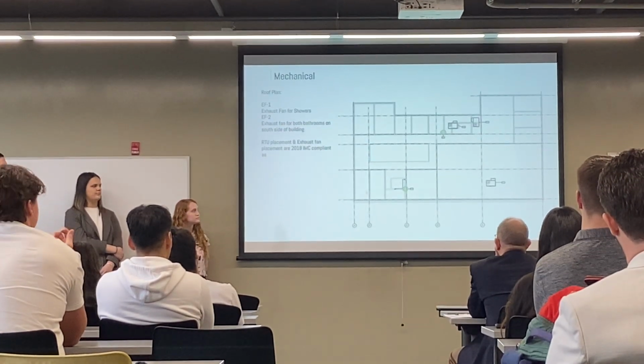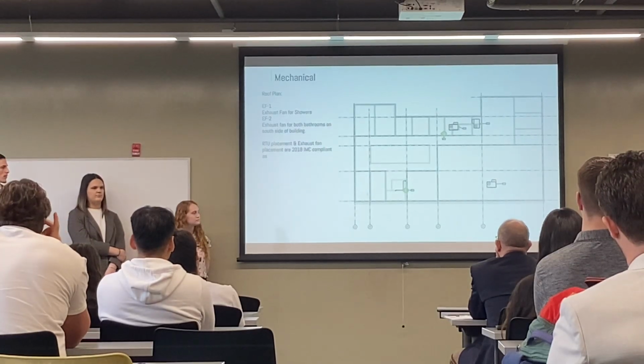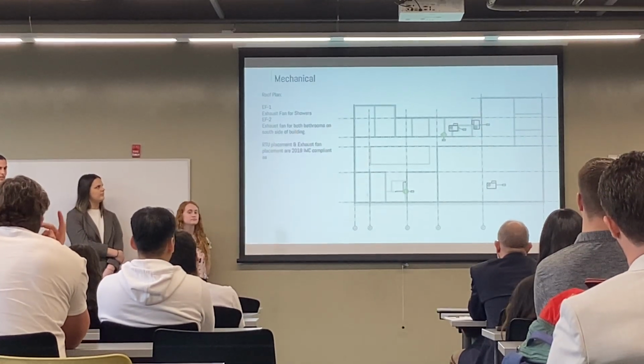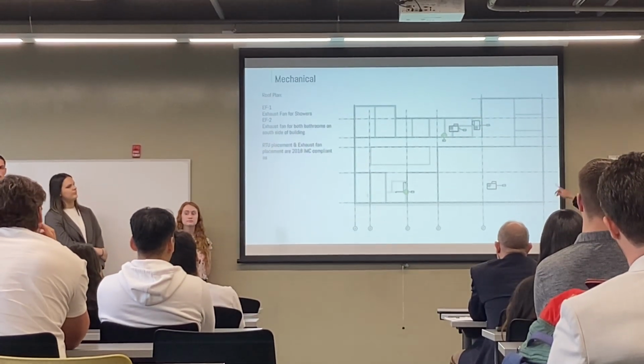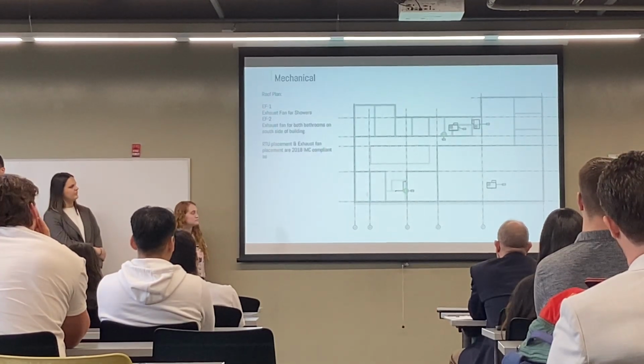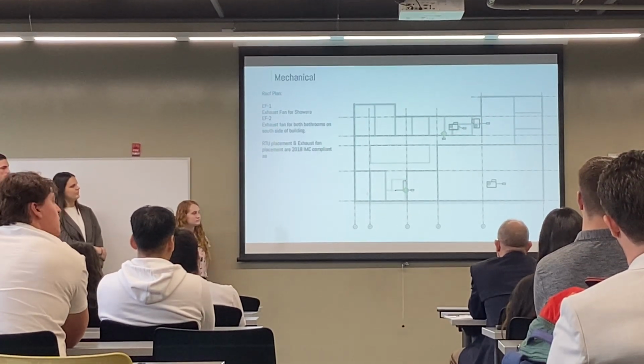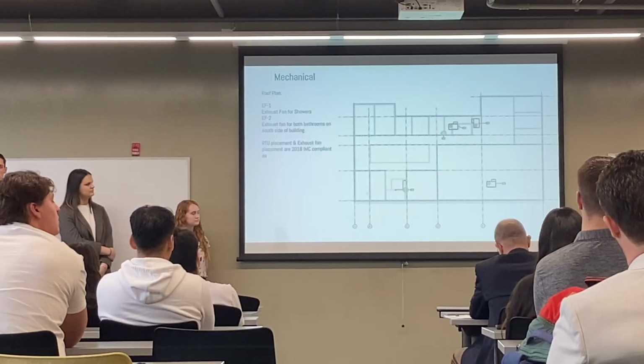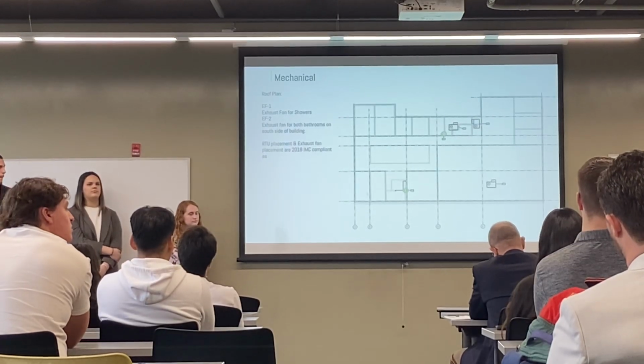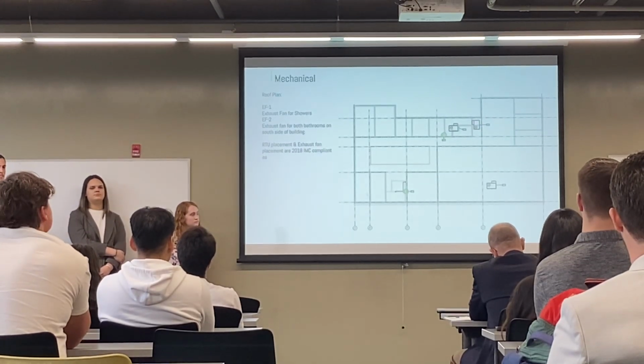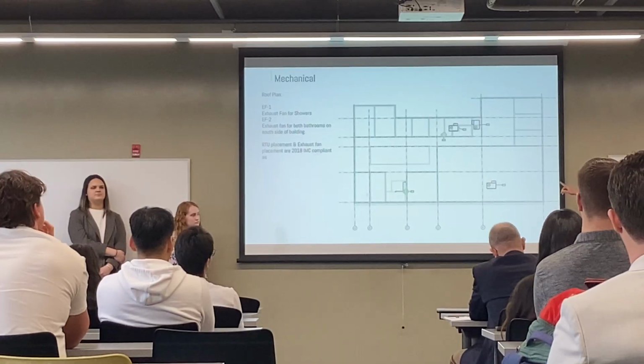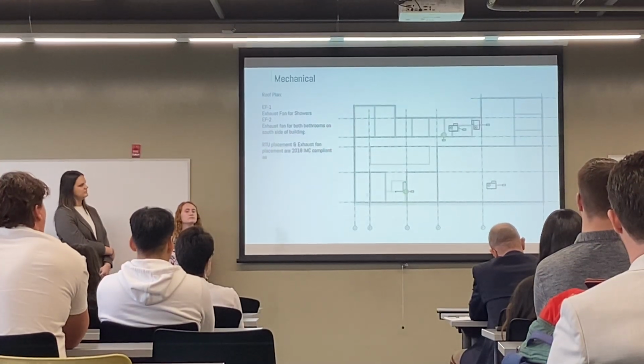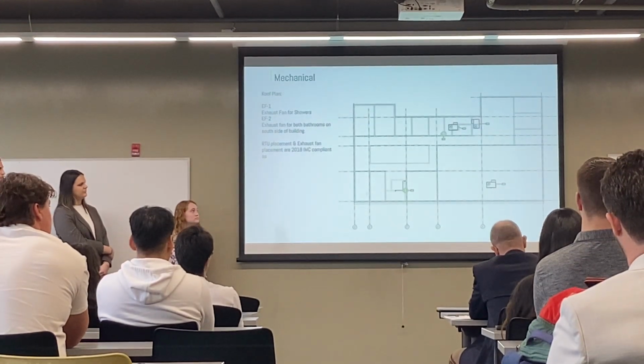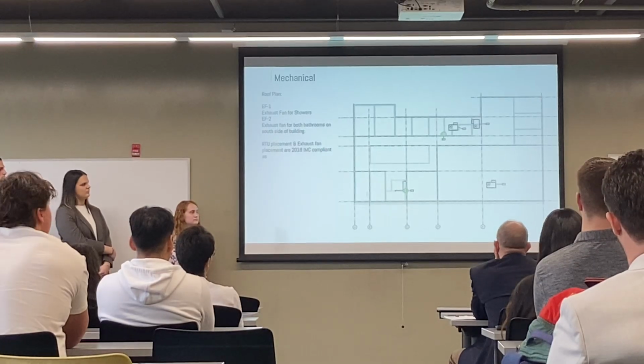And for the roof plan, there's not much here except just the RTU placements and the exhaust fans, which you can see in green. Just an example of a code that we exactly had to follow is that any mechanical exhaust fan that is on a rooftop needs to be around 10 feet away from any air intake. So I know you might see that these are a little too close, but we did get it flagged and checked by the BE I was working with, and it's around 11 feet.